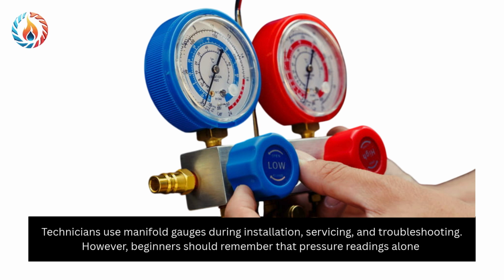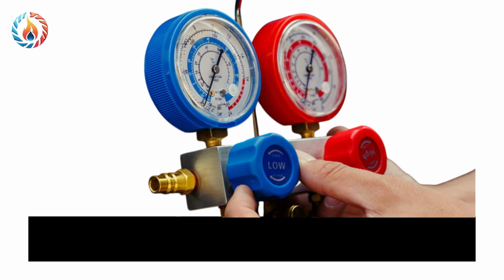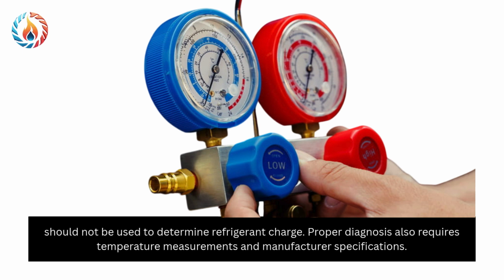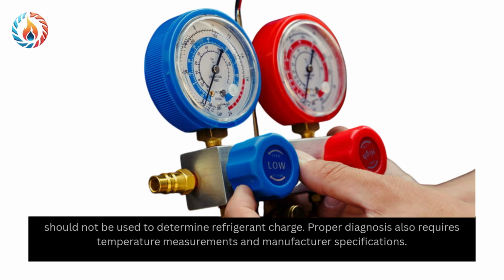Technicians use manifold gauges during installation, servicing, and troubleshooting. However, beginners should remember that pressure readings alone should not be used to determine refrigerant charge. Proper diagnosis also requires temperature measurements and manufacturer specifications.